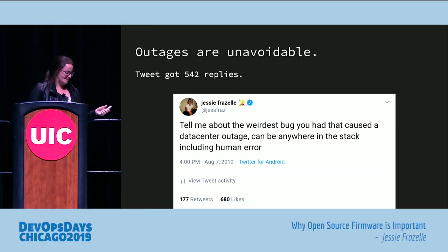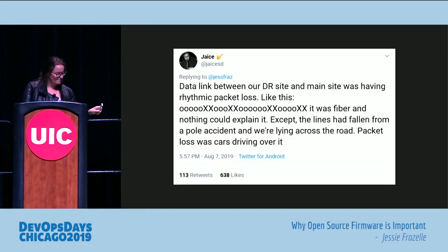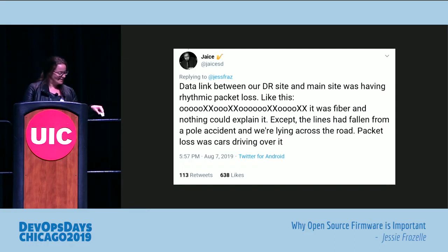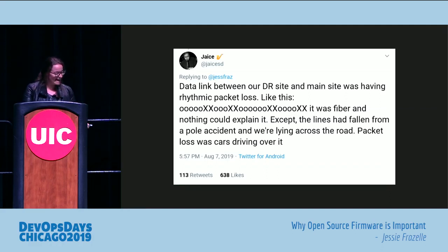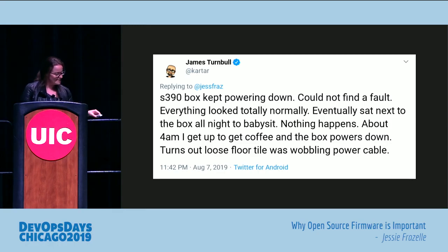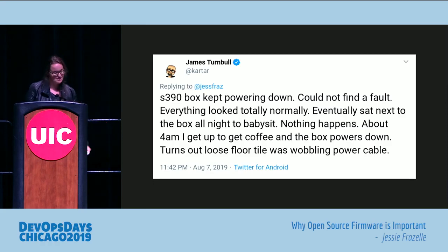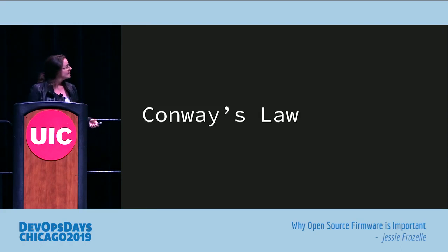Outages in general are unavoidable, and I'm only including this because some are really funny. Data link between a DR site and main site was having rhythmic packet loss. It was fiber and nothing could explain it, except the lines had fallen from a pole accident and were lying across the road. Packet loss was cars driving over them. That is crazy. Another one: S390 box kept powering down, couldn't find a fault, everything looked totally normal. Someone sat next to the box all night. Nothing happened. About 4 a.m. they got up to get coffee and the box powered down. It was a loose floor tile wobbling the power cable.